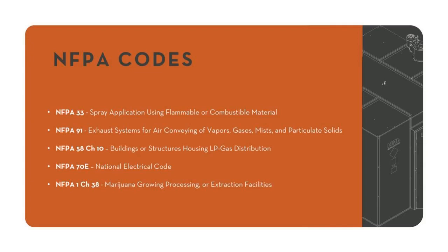They also call for emergency power for the booth. Our booths have emergency backup power to the lights and the sensors as standard, and then you can add additional power to back up the entire booth. But that's something this new code calls for that was not called for in the other NFPA codes: emergency backup power in case there is a power failure. And then they also call for action when you go over that 20% lower explosive limit threshold. So again, we see that code, a very important one, and we'll see it again as well.